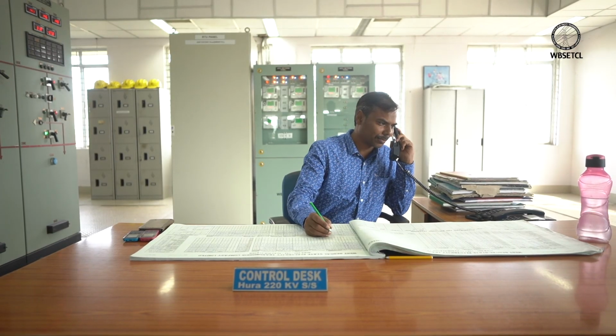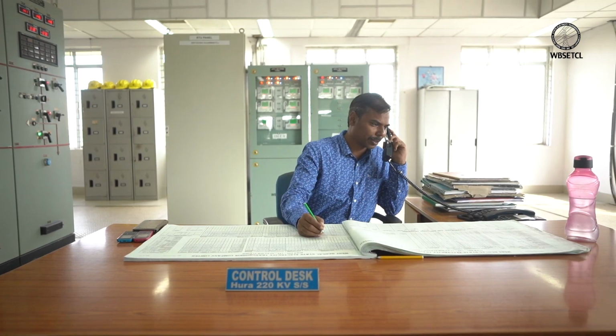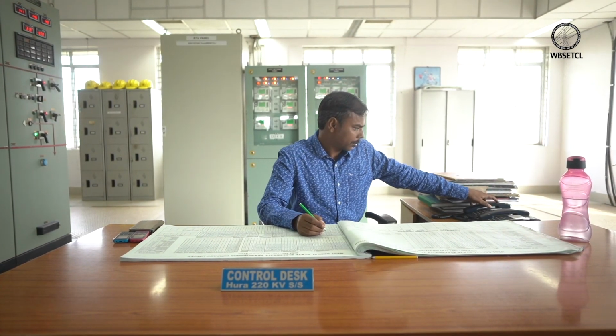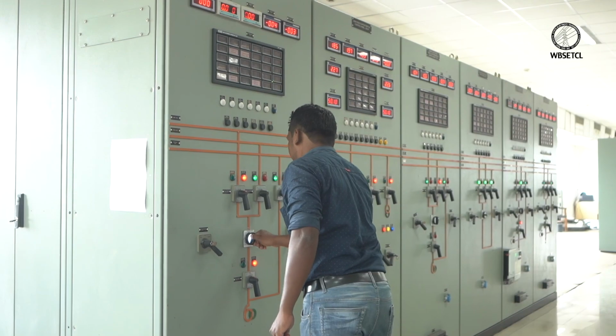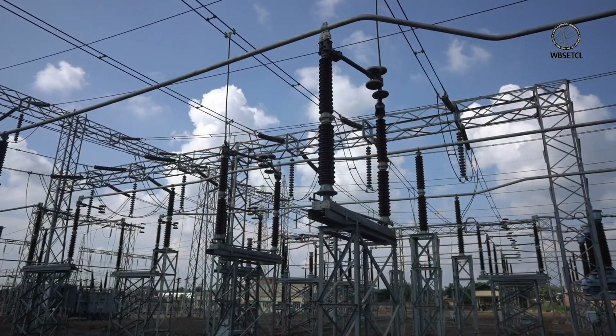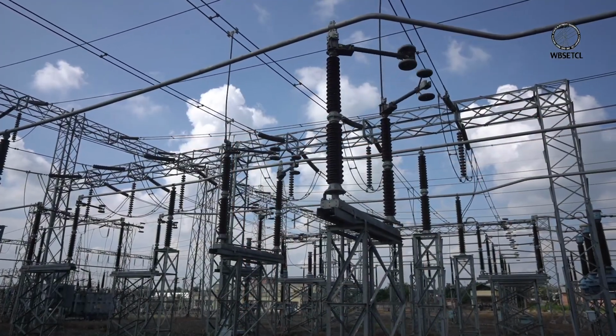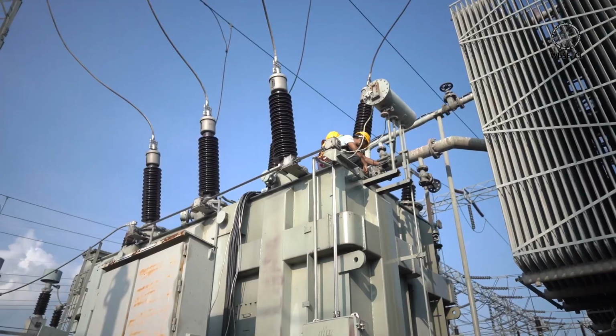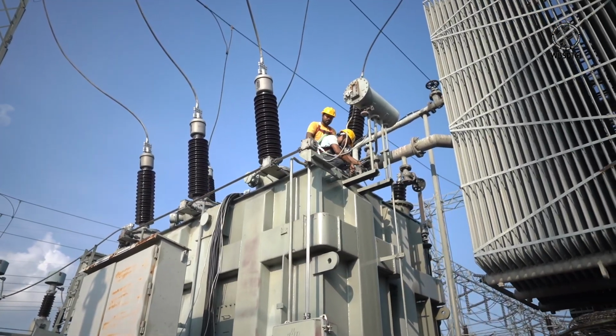Here we are providing the shutdown of a 160 MVA transformer for replacement of oil surge relay as a part of preventive maintenance, ensuring maximum safety of electrical workers following all protocols, in coordination and supervision with the State Load Dispatch Center or SLDC.